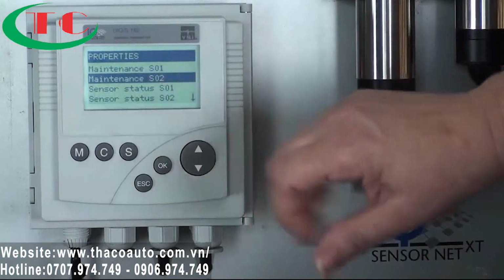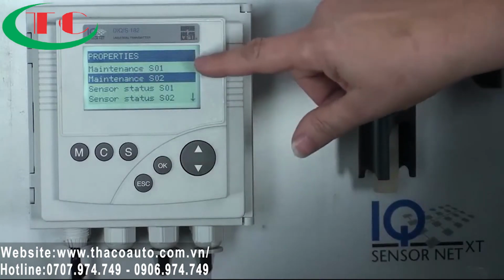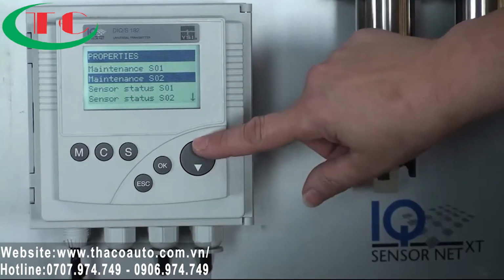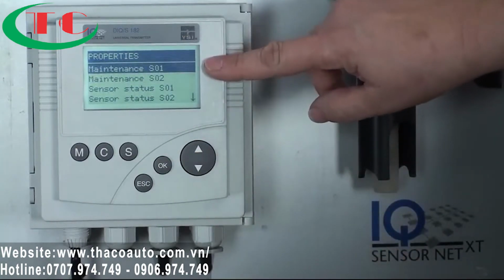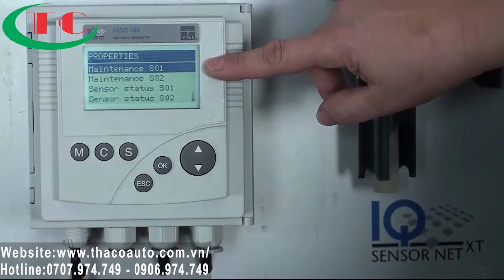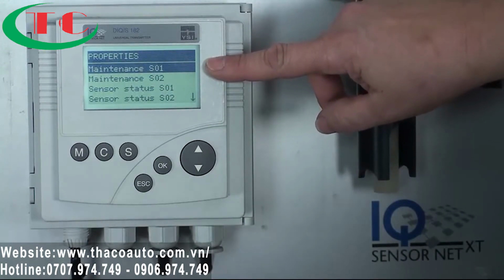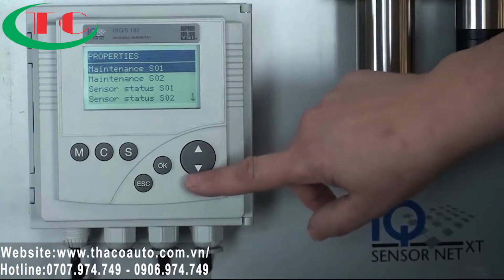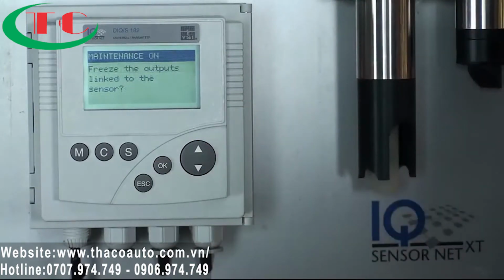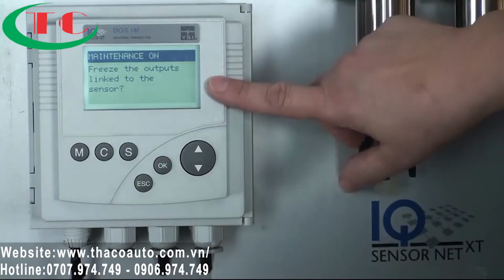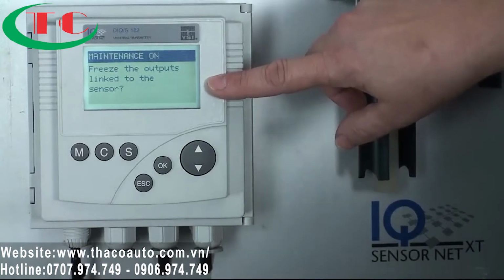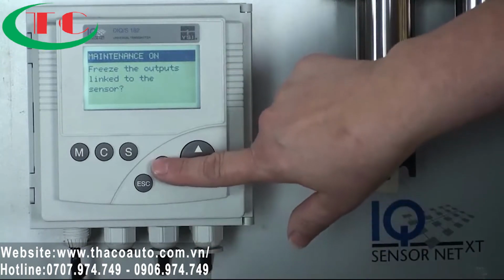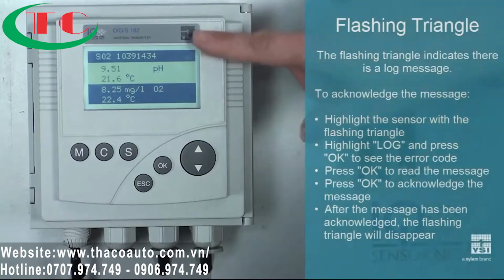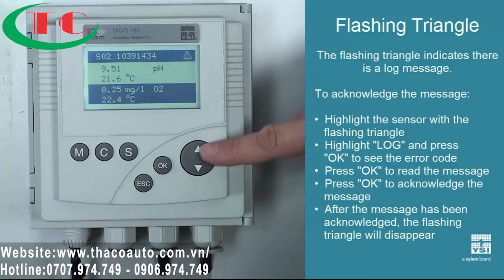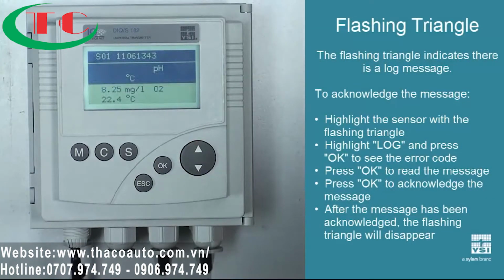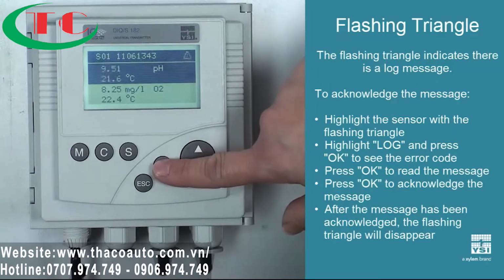So from the main menu you press the OK button and it's going to take you into a menu. It's called Properties. And from here we can put the sensors we have installed into the maintenance condition. It'll freeze the outputs and links. I can show you, press the OK button. It asks you, do you want to freeze the outputs linked to this sensor? If I say OK, you can see that sensor 1 is now flashing. So it's in maintenance mode.